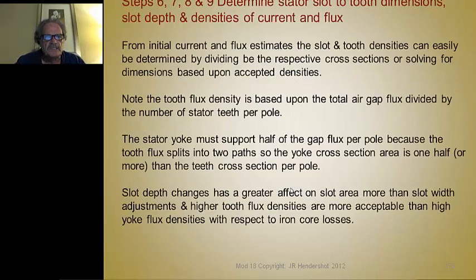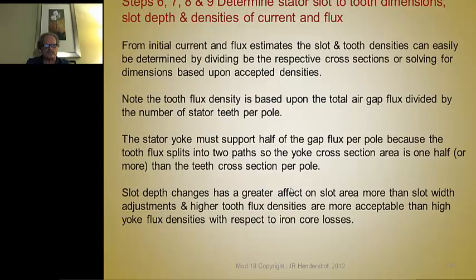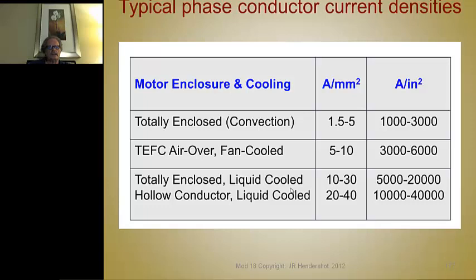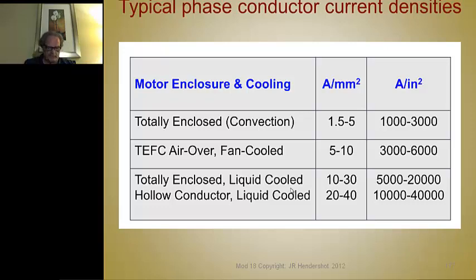These comments apply to all machine types discussed in these lectures. For steps six through nine, we determine the slot tooth dimensions — slot depth and the density of current and flux. This is simple arithmetic once you know the flux: divide the total lines of flux by the cross section to make the tooth and yoke dimensions thick enough for acceptable flux densities. For current densities, here are accepted practices for current densities in the conductors. If you have parallel paths, this assumes the current is split evenly, but forcing equal current sharing through parallel paths can be a serious problem.